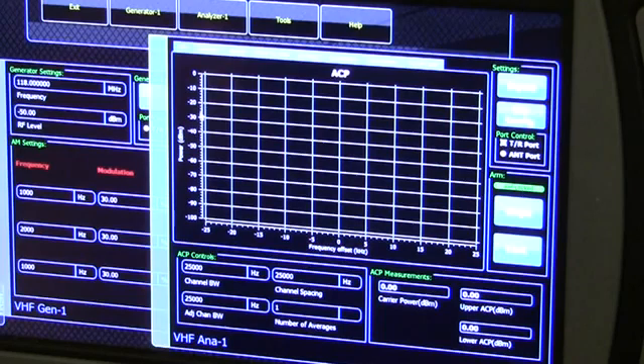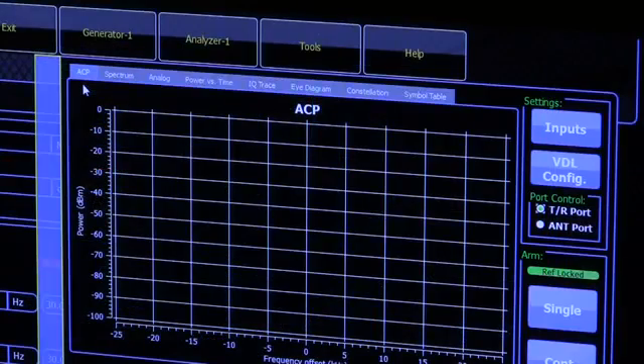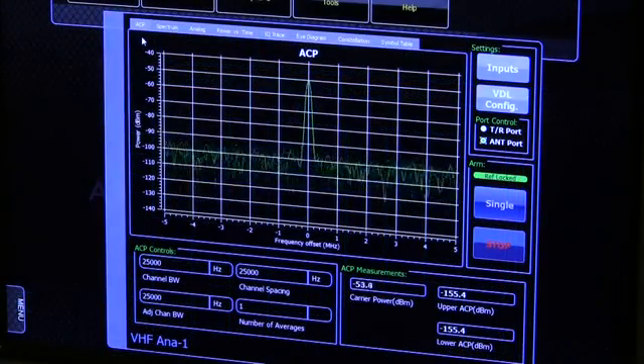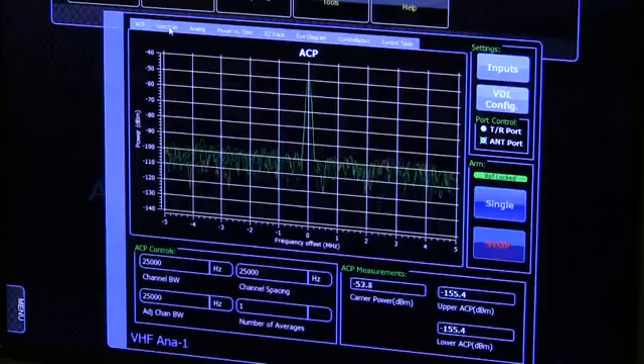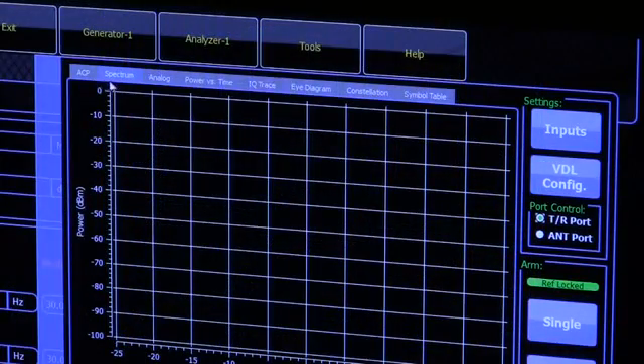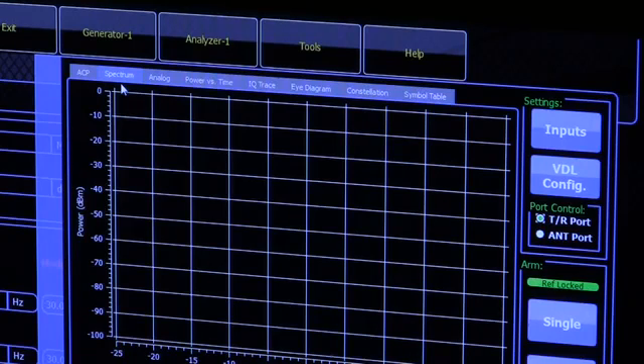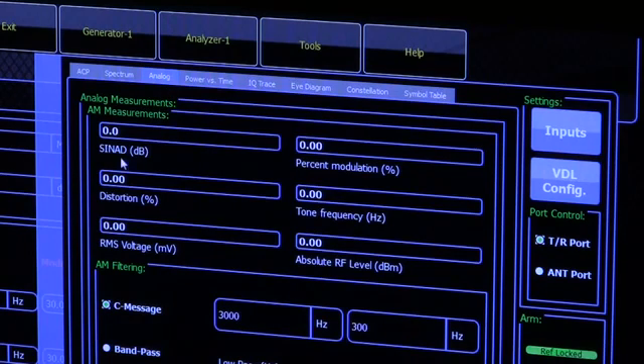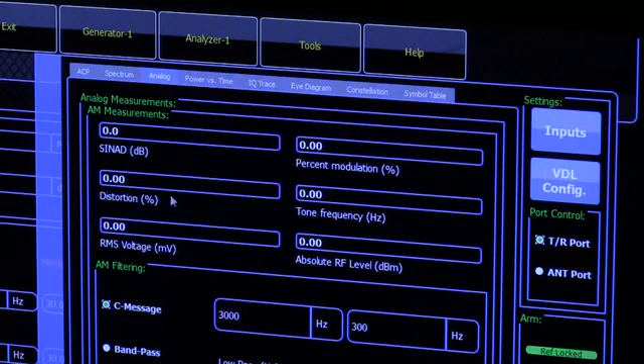Across the top of the VHF ANA1 screen are the following analyzer functions. ACP, Adjacent Channel Power, measures the way a channel of interest distributes power across its bandwidth and its two adjacent channels. Spectrum Analyzer provides a graphical display and measurement of peak power levels across the frequency domain. Analog Measurements is a control tailored primarily for measuring the quality of a single modulated signal — it measures SINAD (signal-to-noise and distortion ratio), audio distortion, percent of modulation, and tone frequency.